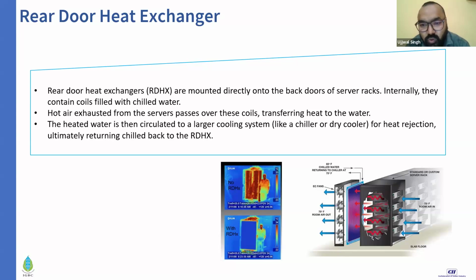So how do we do this? Instead of placing a chiller circuit or cooling tower circuit to a CRAH or in-row cooling system, we place a door behind the server. That door is made up of coils and lots of small EC fans. The EC fans circulate the hot air over the coils, and since the coils are supplied with chilled water, they cool the air right then and there. The air heats up in the server, and by the time it's exiting, it's already cooled again. So you don't require any plenum or containment in this process. This is by far one of the most efficient cooling processes for data centers, only lagging behind liquid cooling systems.